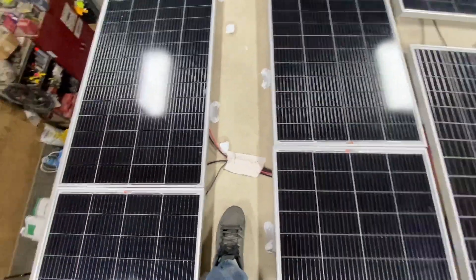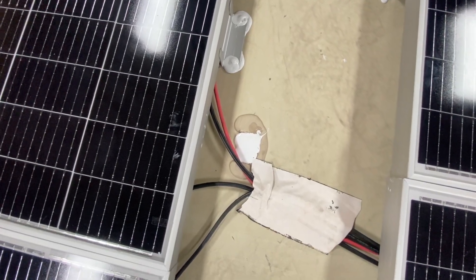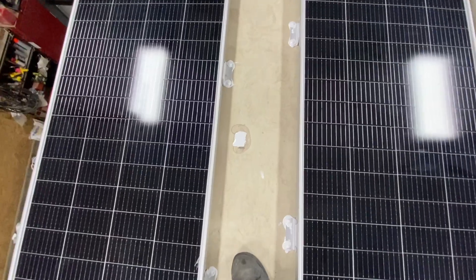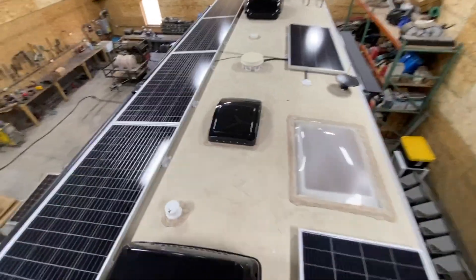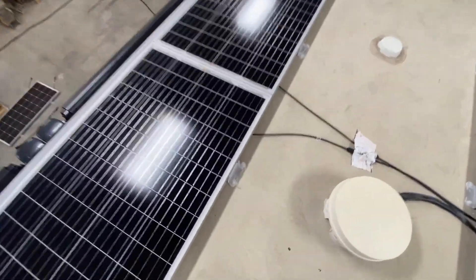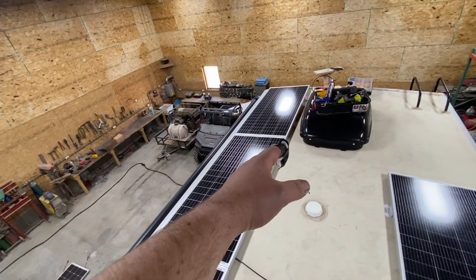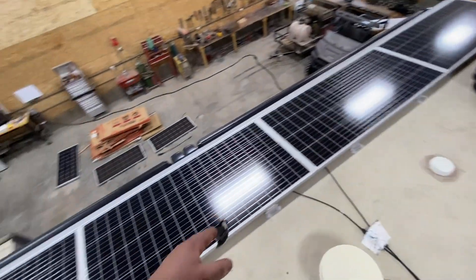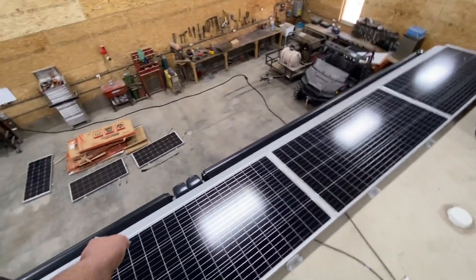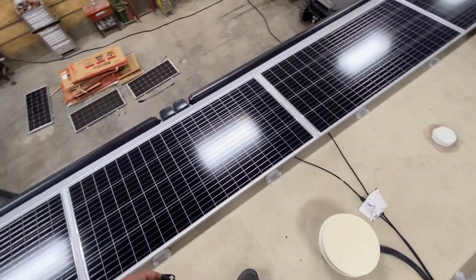The nice thing is when we're upwards of 200 volts, we can still use the same 10-gauge wires. You can see where we took them off the old brackets and filled the holes with Dicor so nothing's going to leak. It was also nice to get confirmation that our securing method worked really well — we had to take screws out of this edge and lift the panels to reconfigure just on that one side, and we didn't have to take off the other side.